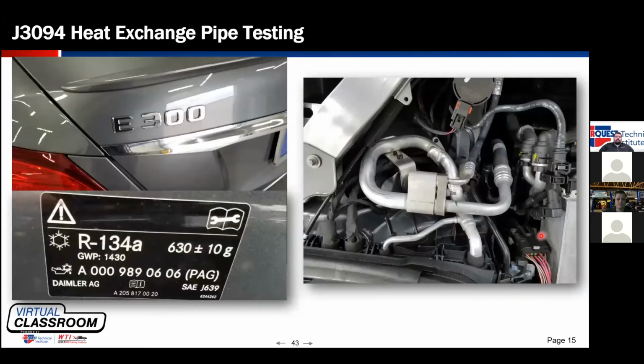One of the components that has been added to a 1234YF system, the vast majority of 1234YF systems have these, some 134A systems have them, is an inline heat exchanger. You can see this is under the hood of a Mercedes, and we can see right here, the suction line and the liquid line come together, run pipe in a pipe, with the suction line down the middle, the liquid line on the outside, till they split to go into the evaporator.